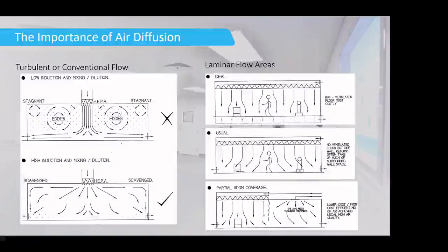Unfortunately, you need a usable space, with equipment and people operating in there. So any clean room is a trade-off between the ideal scenario and practical implementation. Usually you'll have general diffusers squirting air over half of the laboratory, and then dedicated laminar flow hoods over sensitive areas like production or filling lines. We also want to make sure the air is constantly being churned up. We don't want stagnant air where particles can settle and land on a product or contaminate the process, so we keep the air turbulent so particles remain buoyant and get captured.